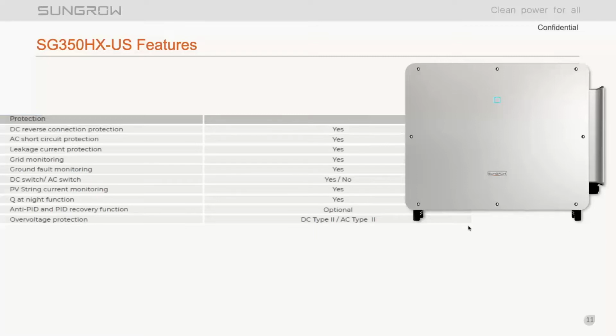As with the 250 and even the 250's predecessor, the SG125, we do have anti-PID and PID recovery, as I mentioned before. Now the data sheet says that it's optional. The only reason it says optional is because it's a toggle option that's in the HMI app. Every inverter comes equipped with that particular hardware and software to control your PID. And then, as with all of our string inverters, we have type 2 DC and AC surge protection.